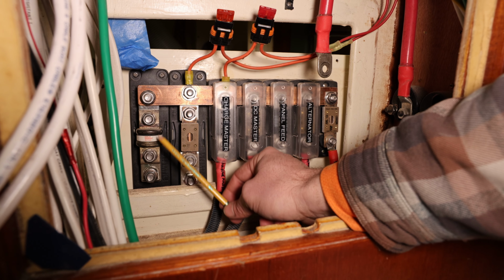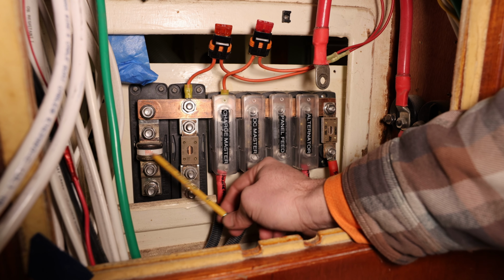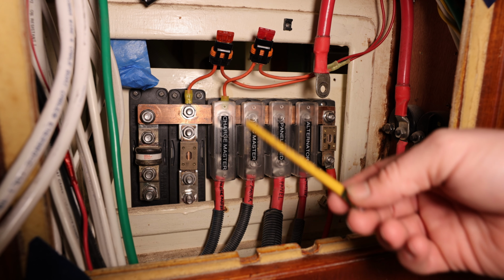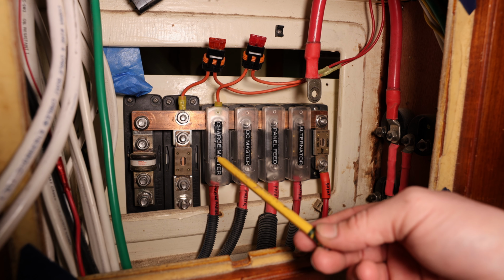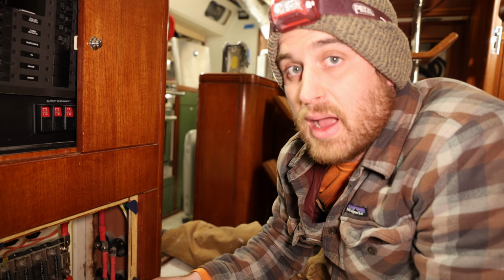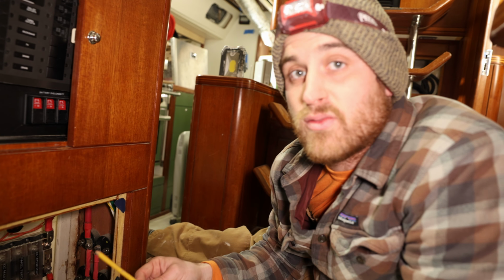We had a massive Class T fuse going to a bow thruster disconnect switch just through this bulkhead, then a 4/0 cable run 25 feet from the center of the boat all the way to the bow. That's a massive amount of voltage drop trying to run power all the way up there. We saw that when our batteries had low charge over the summer, if you used the bow thruster too much without the generator on, some of our electronics would flash.